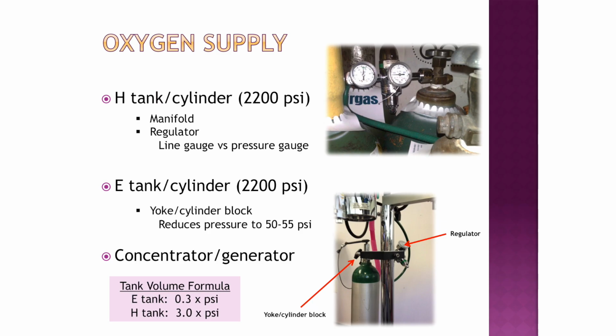With the H tanks we used to use, there's always a manifold pressure and a line pressure, because anesthetic machines can't use the pressure straight out of those H tanks. We have to reduce it down to about 50 to 55 psi. The E tanks, some have 2 valves, but most only have 1, where that 50-55 pressure reduction is handled right in the manifold. There's also a math problem: 0.3 times the PSI to find out how much oxygen is in your E tank, or 3 times the PSI for the H tanks, if you want to figure out how much you have left.